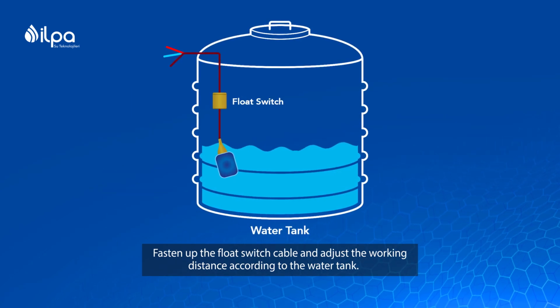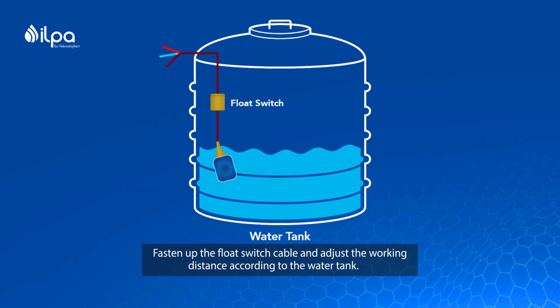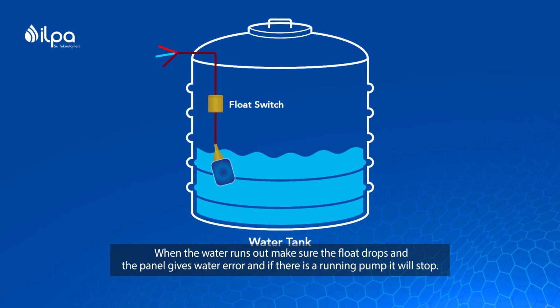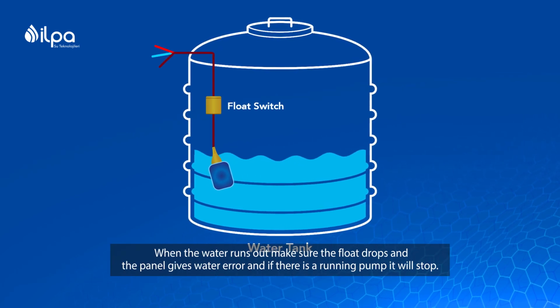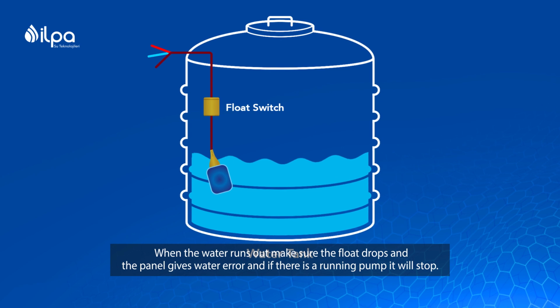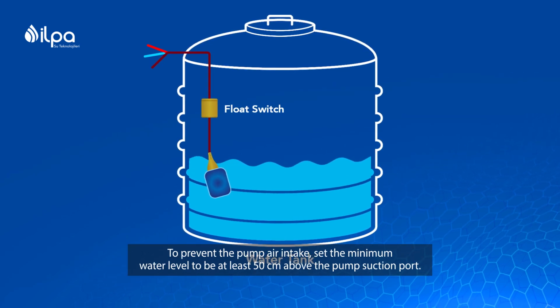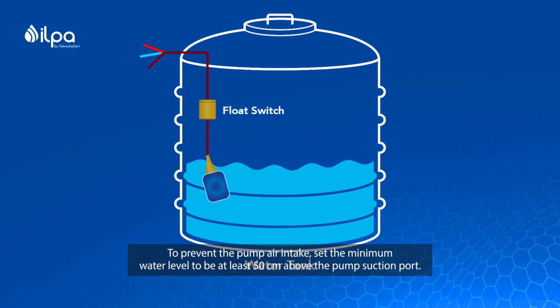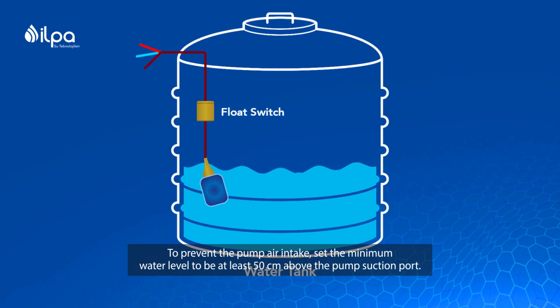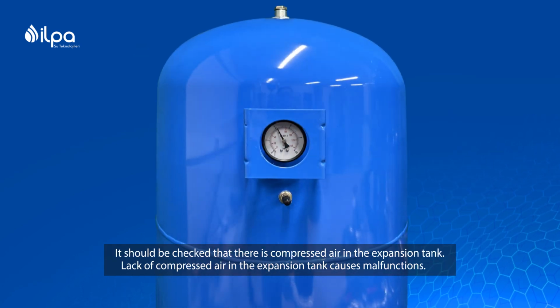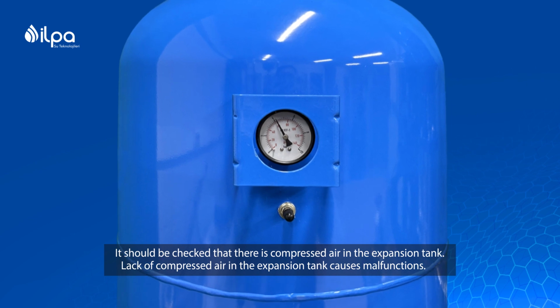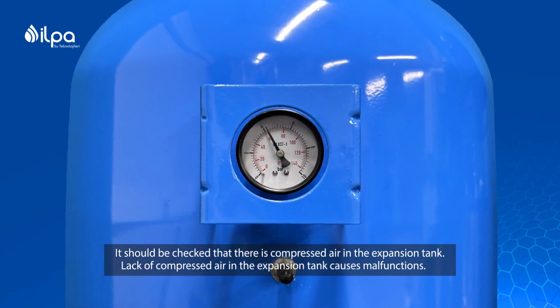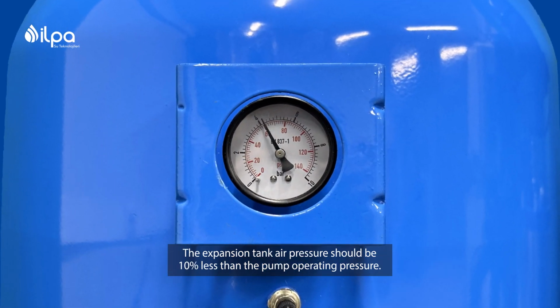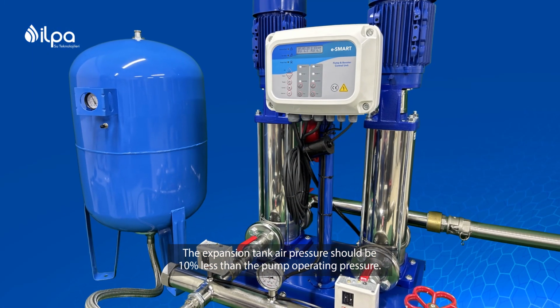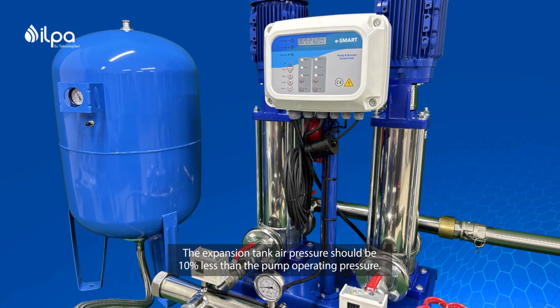Fasten up the float switch cable and adjust the working distance according to the water tank. When the water runs out, make sure the float drops and the panel gives a water error, and if there is a running pump it will stop. To prevent the pump from taking in air, set the minimum water level to be at least 50 centimeters above the pump suction port. It should be checked that there is compressed air in the expansion tank. Lack of compressed air in the expansion tank causes malfunctions. The expansion tank air pressure should be 10% less than the pump operating pressure.